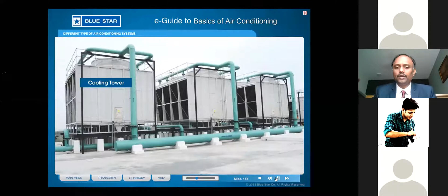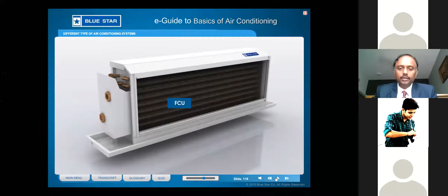From there, you go to each of the AHU rooms on each floor. As you can see, this is the AHU, which is nothing but an air handling unit. The chilled water is taken inside the air handling unit, and then air is thrown, and hence you get the cold air. For small hotel rooms, you have a small type of AHU called a fan coil unit, or FCU. In 5-star hotels, what you see in each room is nothing but a fan coil unit. This is also a part of the chilled water system. There are also chilled water cassette units, like the VRF systems you have, but with chilled water going inside the cassette units. This is also used in some of the malls and some of the office areas. So this is called chilled water cassettes.